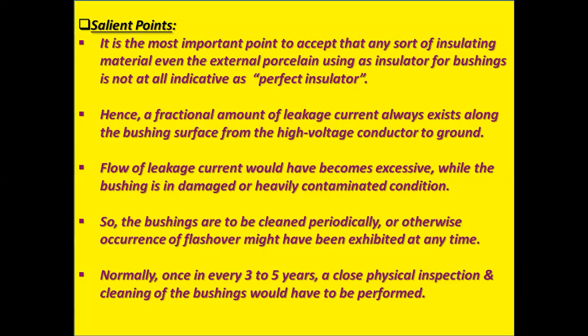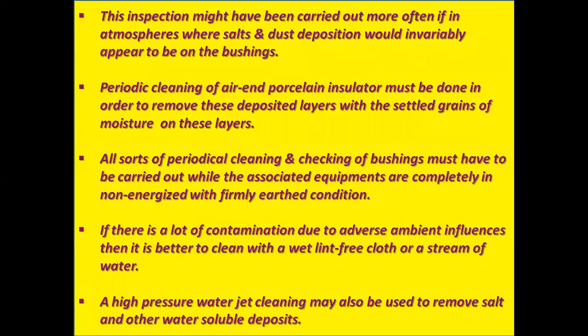Normally, once in every 3 to 5 years, a close physical inspection and cleaning of the bushings should be performed. This inspection might be carried out more often in atmospheres where salts and dust deposition would invariably appear on the bushings.